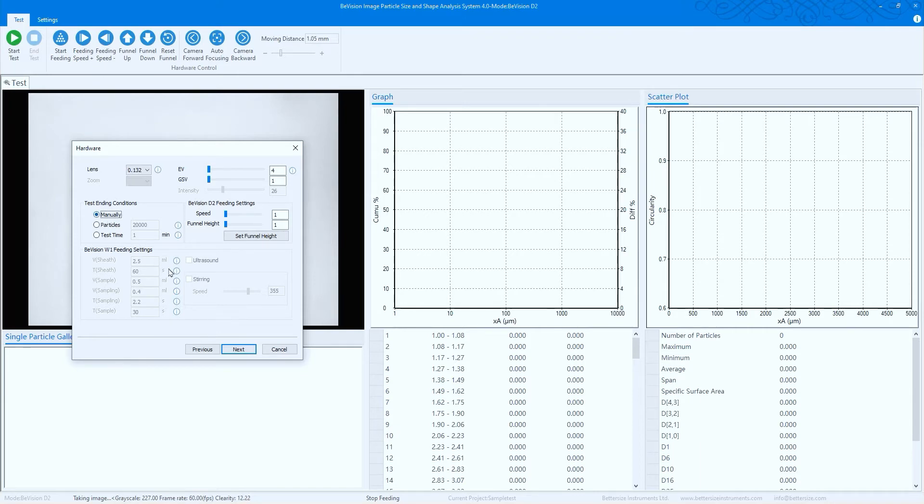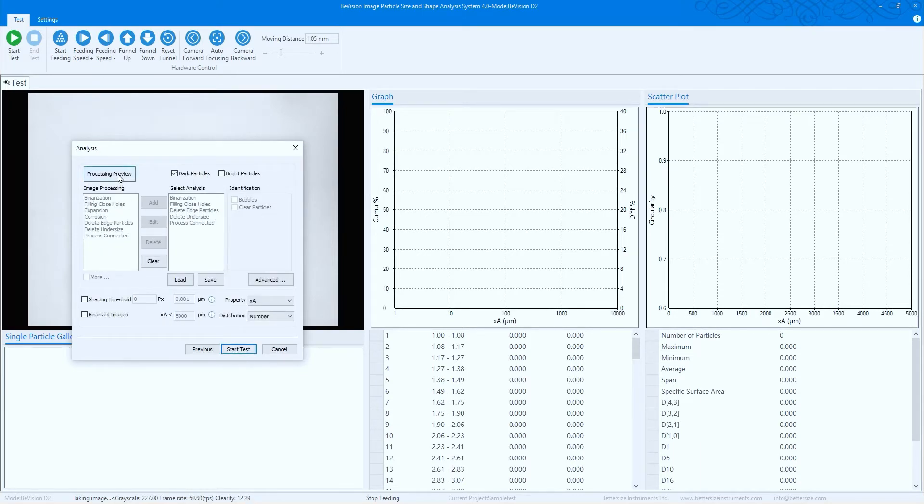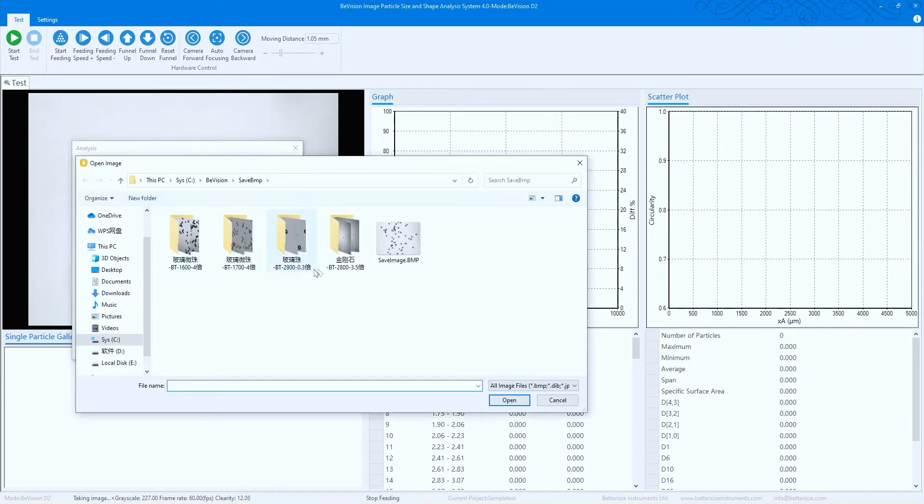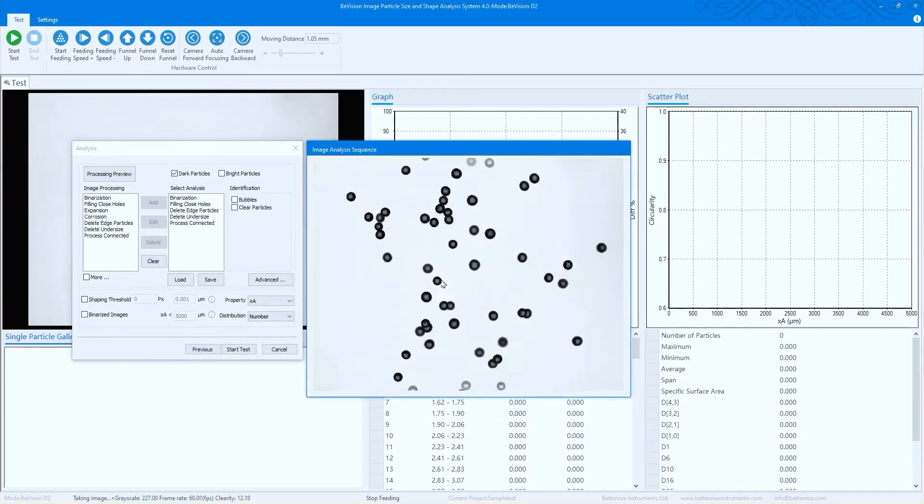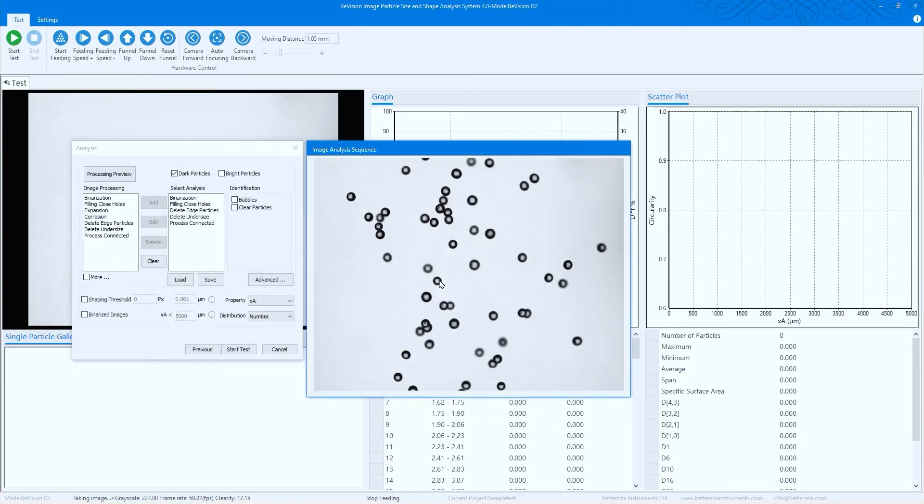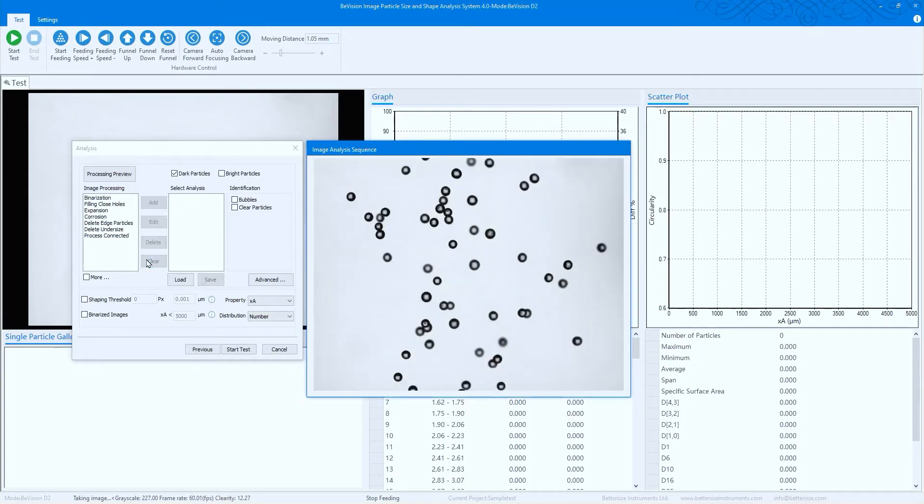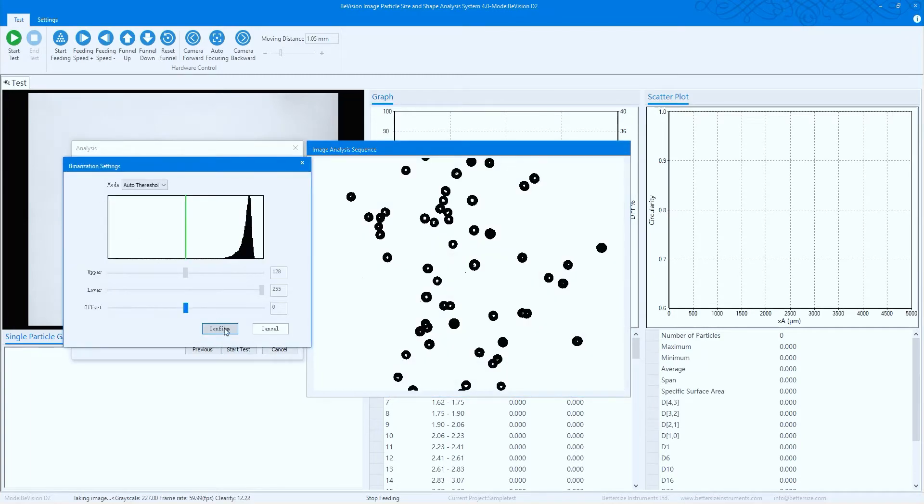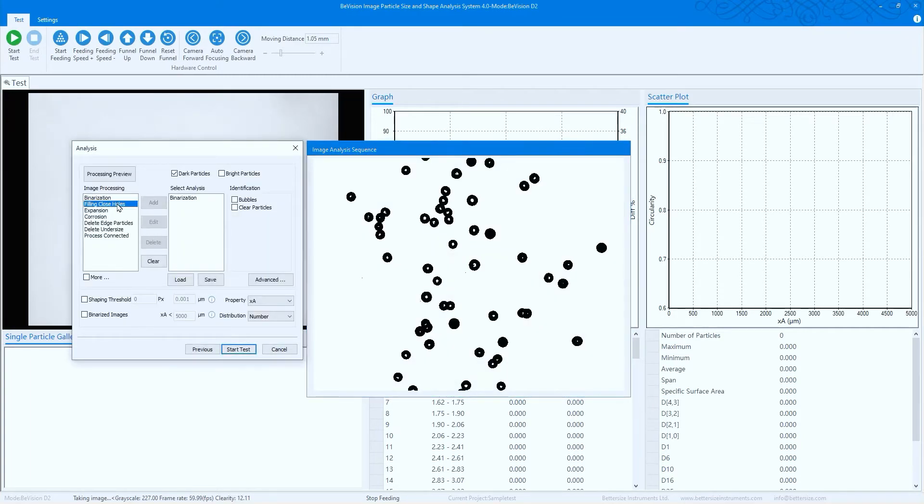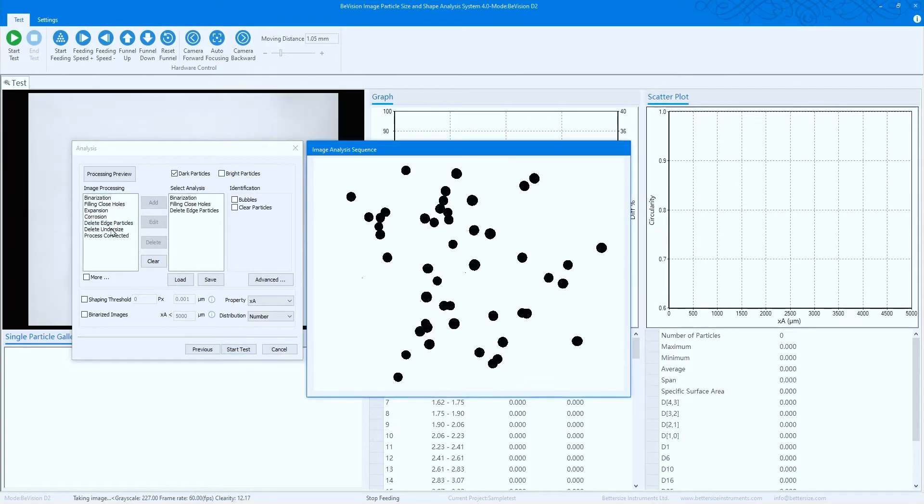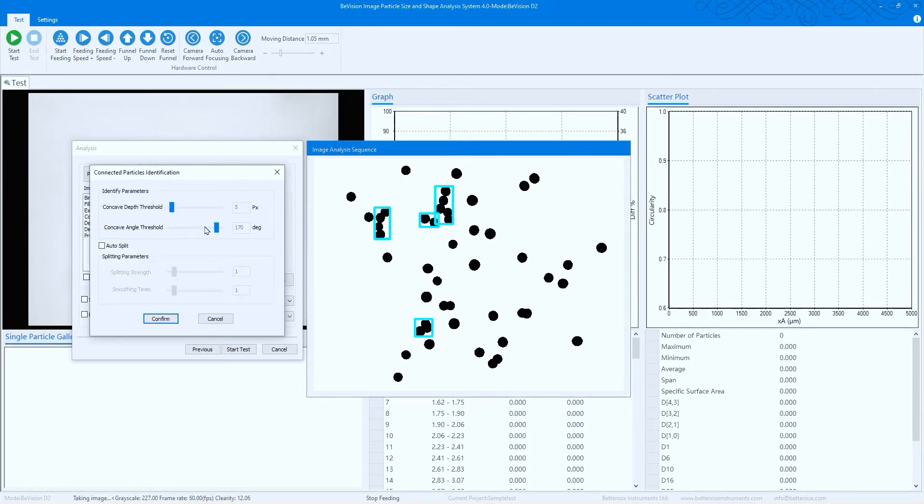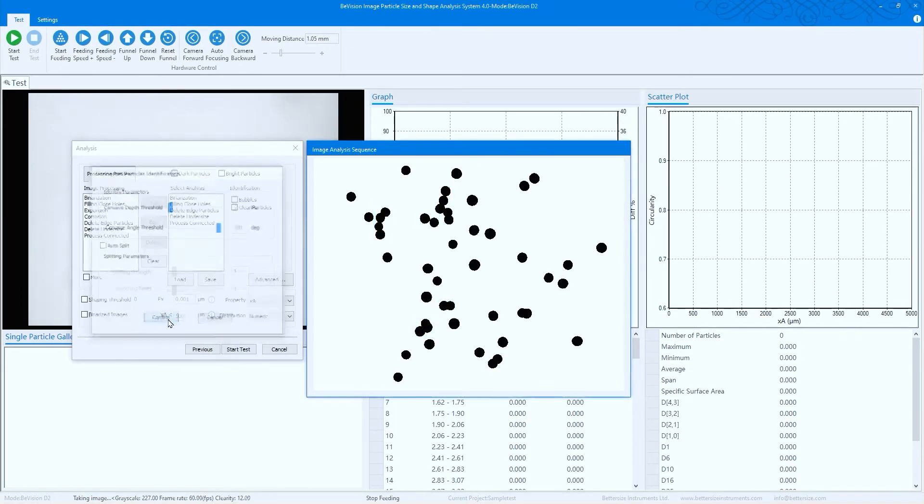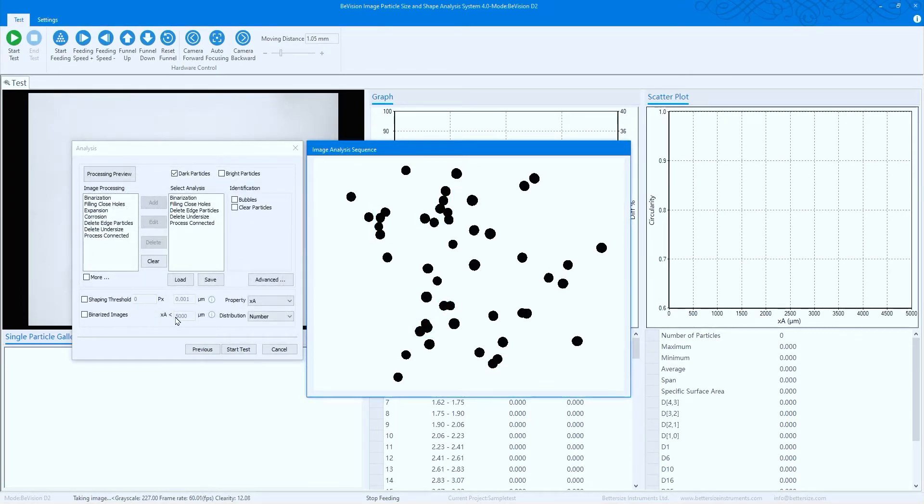Next, process preview by selecting the saved image. If the predefined analysis sequences settings cannot fit your test requirements, you can click clear to remove all analysis sequences, then add binarization, filling close holes, delete edge particles, delete undersized particles, and process connected based on the measured sample. All of these settings can be saved as standard operating procedures for your next analysis.